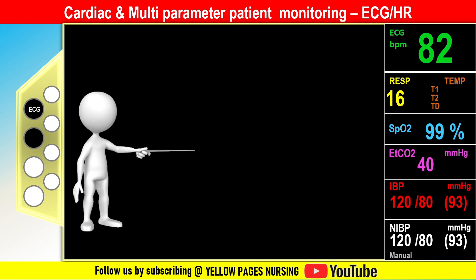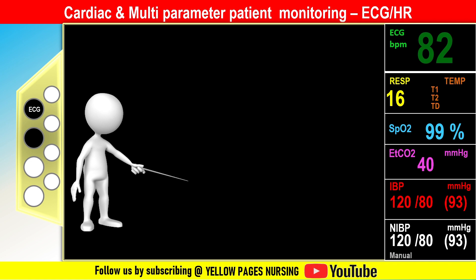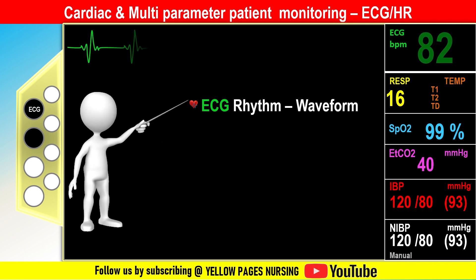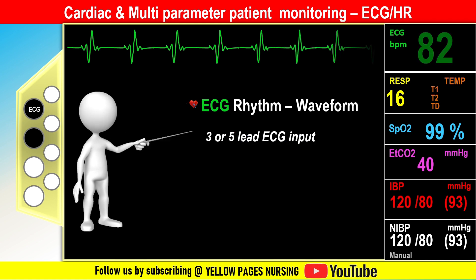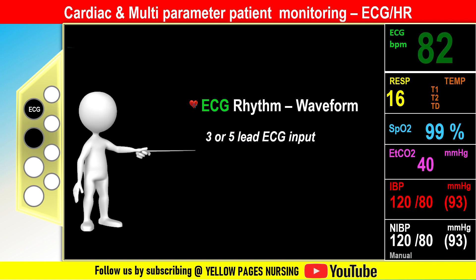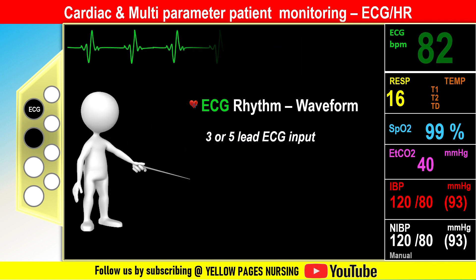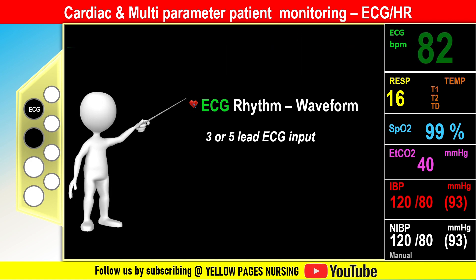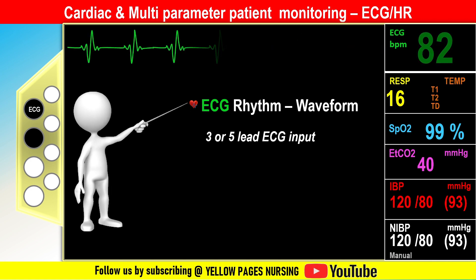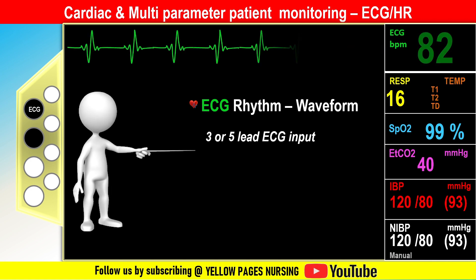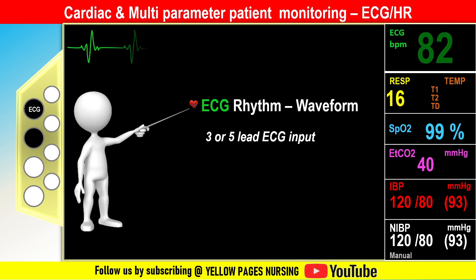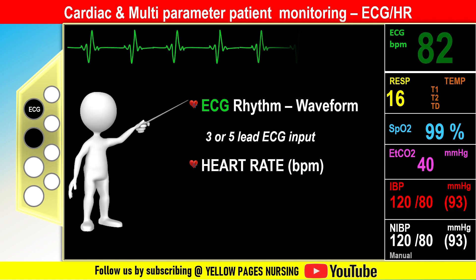Parameters that can be monitored include electrocardiogram, available in three-lead or five-lead mode. ECG electrodes are attached on the patient's chest and the cable is connected to the monitor in order to monitor the electrical activity of the heart, displaying the heart rate and rhythm.